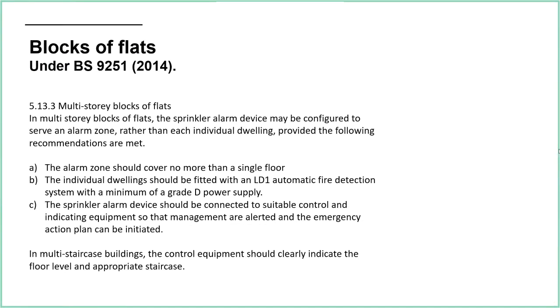C, sprinkler alarm device should be connected to a suitable control and indicator equipment so that management are alerted and emergency action plan can be initiated. So, again, pretty obvious, but you can't just have an alarm device not doing anything. The alarm device has got to be connected to something which is going to feed into the overall building strategy to make the evacuation of the building safe and according to plan.